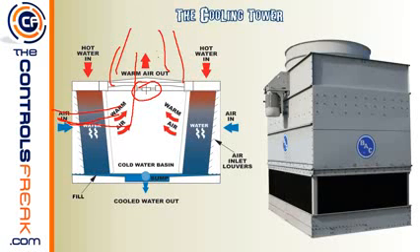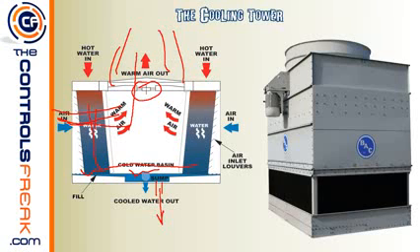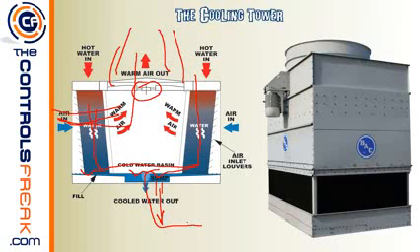Sometimes you'll see big plumes of steam coming out of rooftops early in the morning when it's cool outside — that's exactly what you're seeing, all that hot air coming out the top creating steam in cold weather. As the water falls down it goes from hot to cold. There's a cold water basin at the bottom, typically with one to two feet of water, and one return pipe that sends that cooled water back to the chiller.